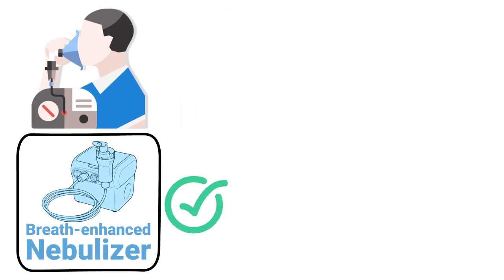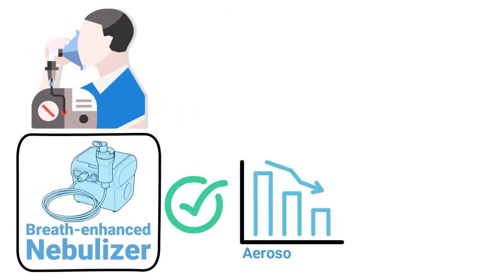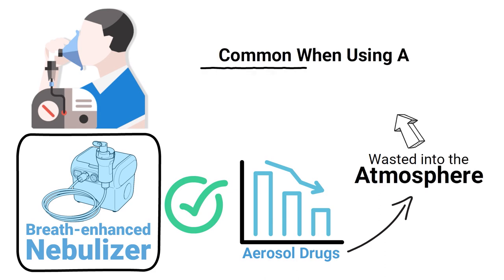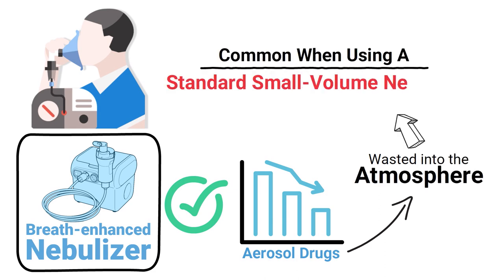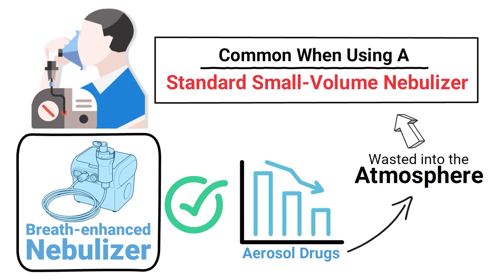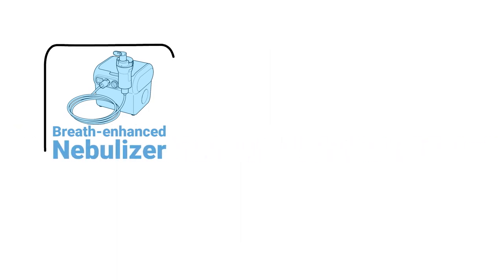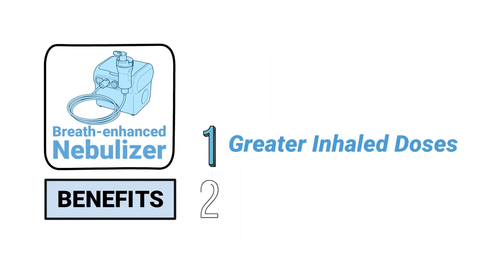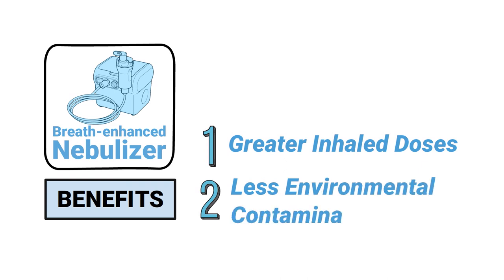This is how breath enhanced nebulizers are able to reduce the amount of aerosol drugs that are wasted into the atmosphere, which is common when using a standard small volume nebulizer. Aside from limiting the amount of medication that is wasted, breath enhanced nebulizers also have other benefits including greater inhaled doses and less environmental contamination.